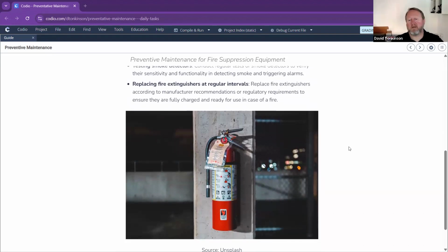They have regular review intervals on those. They have expiry dates. They also have a little gauge on there that is set round. If that is basically in the green area, we're laughing, that's good, we can check it. If they've been discharged, yes, it tends to drift into the red area, at which point that needs to be replaced. So we need to get those things sorted. So make sure they are ready for use in the right location, not used as door stops. So many people in data centers grab one of these, stick it by the door, leave the door open. Okay, you're not helping the air conditioning, you're not helping health and safety. They basically need to be left on the wall where they're supposed to be.